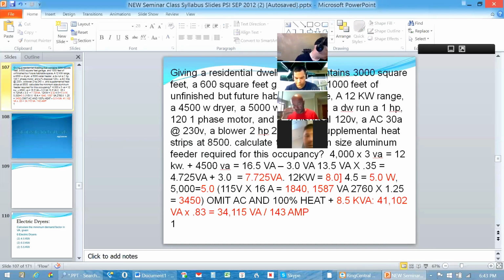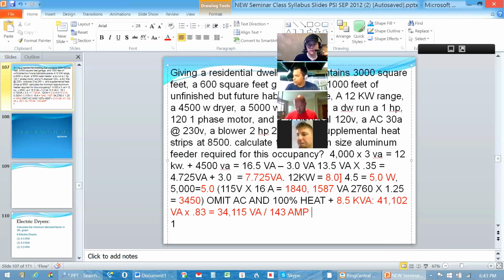the 135, which is what a 2-aught is, we just missed it. So a 3-aught at 155 amps would be the correct aluminum conductor there. I'll make sure I got that right. Yeah, 155 amps. I'm looking at 3-aught then as a residential feeder there. That's a lot to assimilate all at one time, but that's the worst that they could give you on standard method calculation. That's every bit of it all in one example.